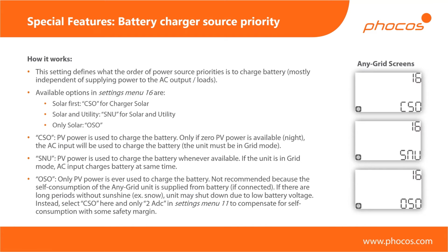So now, conceivably, what could happen if you're living in a region where you might have snow during the winter, obviously that depends on where the system is installed. It's not going to be a huge issue around the equator. But if you're living in North America, for example, or in the mountains, it will be. And let's say you want to only use solar energy to charge your battery. Well, then you would take the only solar setting, for example. Or what will happen is eventually, if you do have snow on your PV array, and there's literally nothing at all coming in from your PV side, well then, slowly but surely, the AnyGrid inverter will drain your batteries over a long period of time.